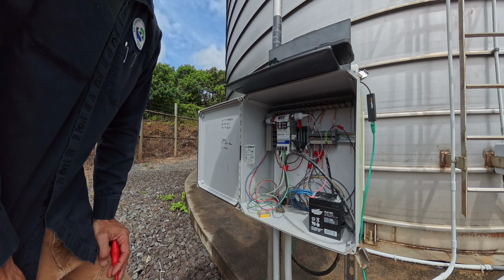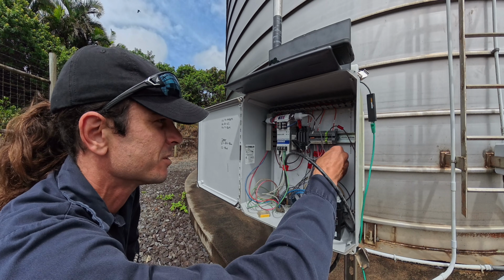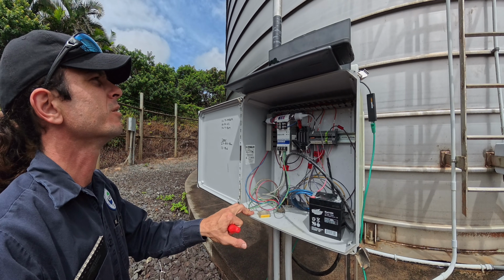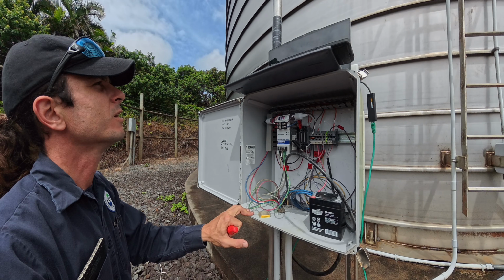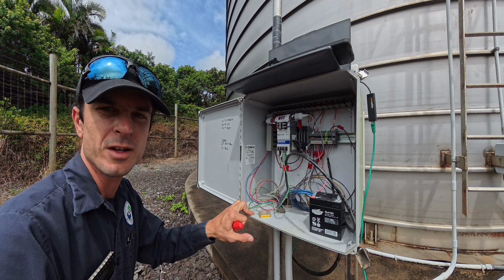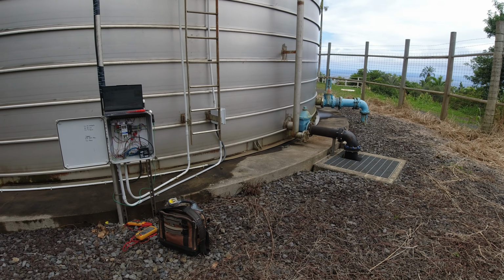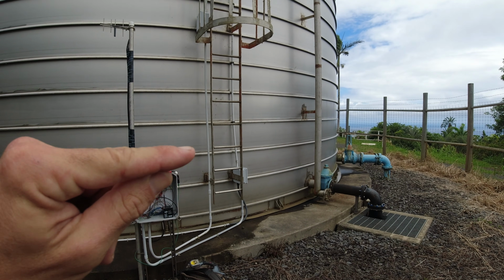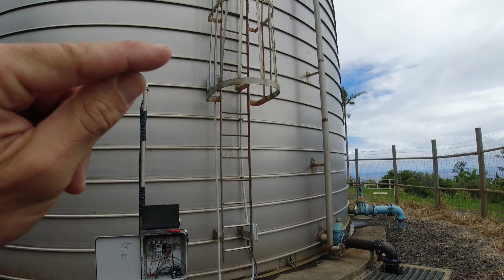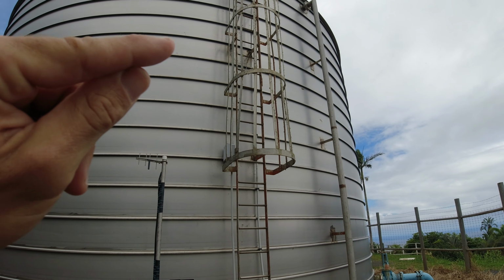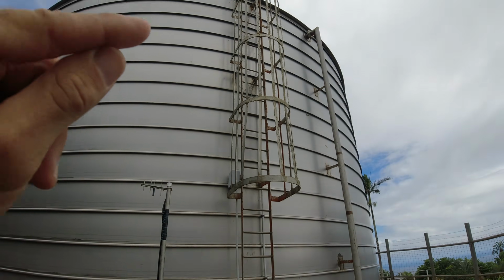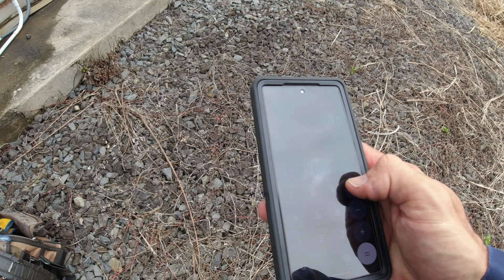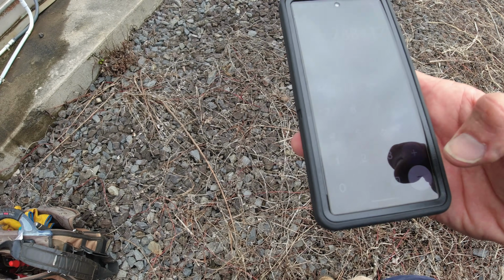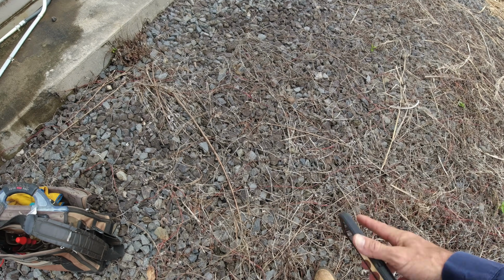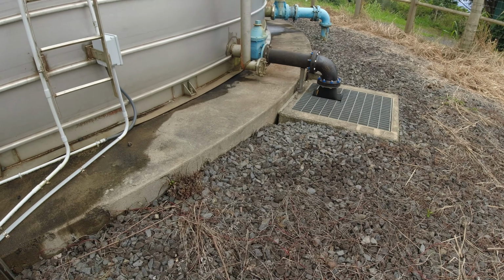And it is bouncing, but barely. I think I'm just going to leave that shield off for now, and we'll let the customer know that it could be on its way out. Okay, and then I want to climb up the tank and see for sure exactly how much water's in there. Each of these rings is 18 inches. 1, 2, 3, 4, 5, 6, 7, 8, 9, 10, 11, 12, 13, 14, 15, 16. 16 times 18, 288 inches divided by 12. So it's 24 feet tall. Should be about 6 feet of air from the top of the tank down to the water. Let's climb up and see.